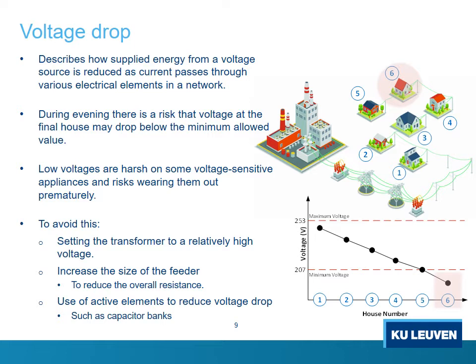However, if the distributor sets the transformer voltage too high, houses close to the transformer may sometimes experience voltage above the maximum allowed limit, which also risks damaging appliances. Most transformers at the distribution level cannot vary their voltage dynamically, so adjusting the transformer requires a truck visit and possibly a brief local blackout.